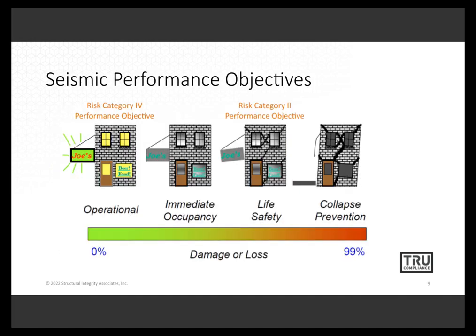We know generally the performance objectives for Category 4 buildings: depending on the level of earthquake, there are different performance objectives. Operational is the goal objective for Category 4 buildings under the design earthquake, and immediate occupancy on the max-credible earthquake. Other more everyday buildings that are Risk Category 2 will have more of a life safety goal. The seismic non-structural requirements will vary, and those are generally represented with an importance factor for the components, which we'll discuss later.